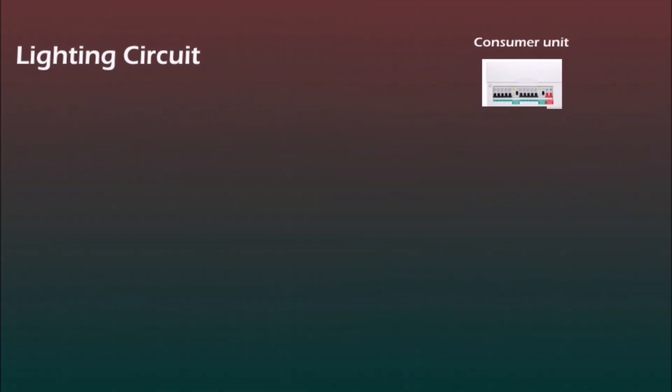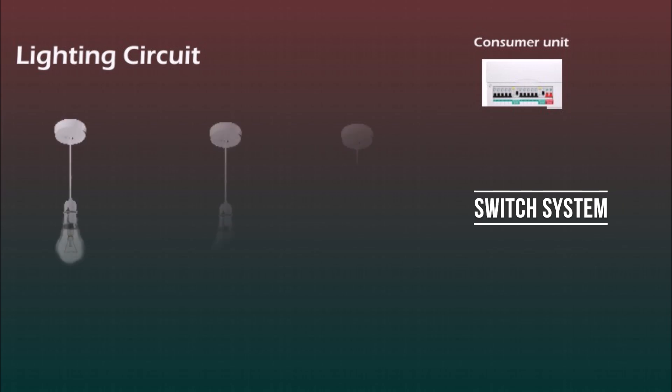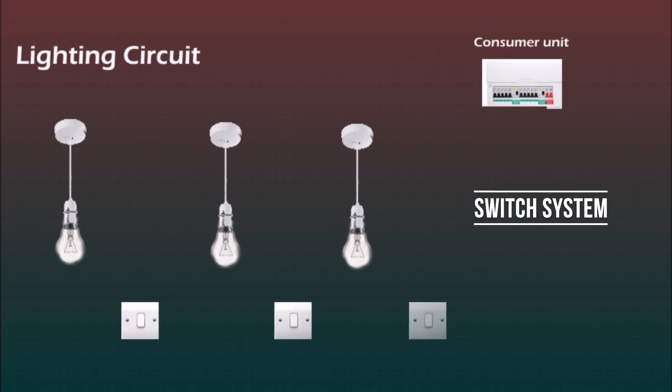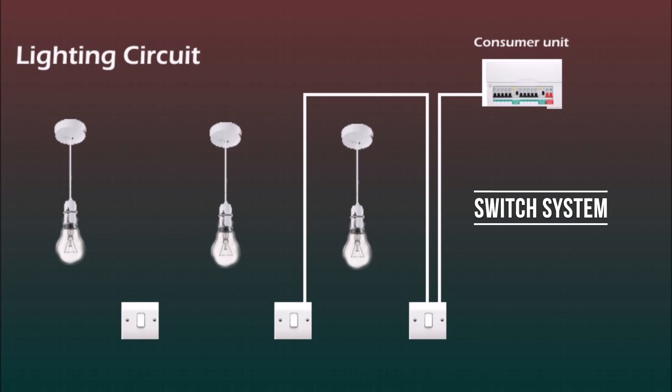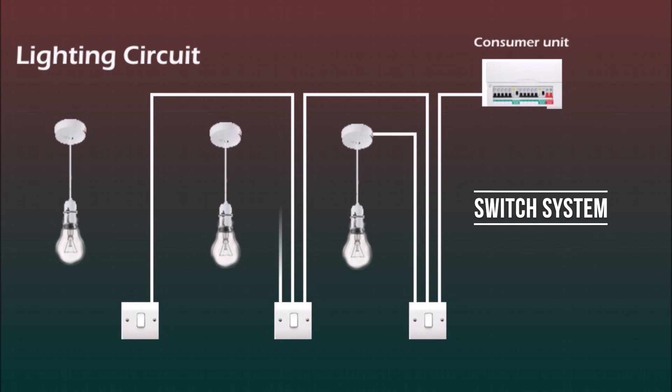And there's a third method, this is my favorite, the switch system. So the cable from consumer unit instead of going to the ceiling rose or junction box goes to the first switch, then from switch to switch and the point where you split the cables is at the switch. Obviously it requires a deeper back box to accommodate all the wires and connectors, but the advantage of this system is that you don't need to use a stepladder if something goes wrong as all the connections are at the switch.